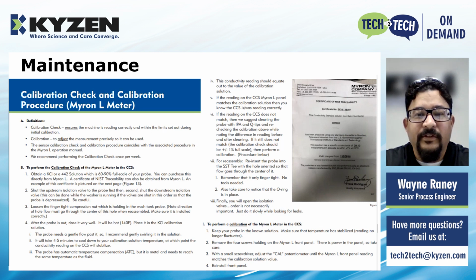The first thing we want to do is a calibration check. This is the calibration check procedure in the CCS operation manual. If the calibration check is out of spec, then you can clean the probes and perform the calibration check again to see if there's a difference before and after cleaning.